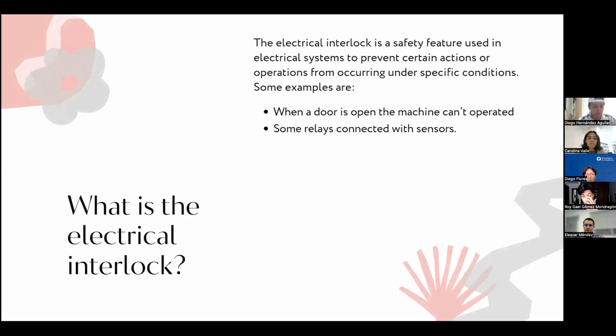What is the electrical interlock? The electrical interlock is a safety feature used in electrical systems to prevent certain actions or operations from occurring under specific conditions. For example, when a door is open, the machine can stop, or some relays connect with sensors that stop the operation of machines.